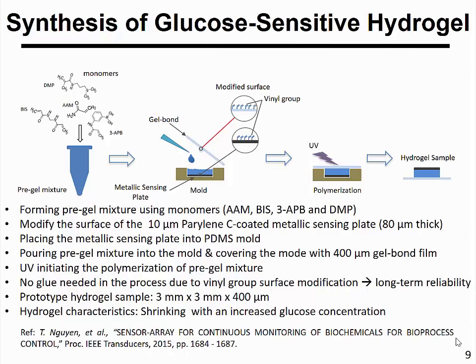An important design aspect is that during the whole process, we do not need any glue to secure the position of the sensing plate or the hydrogel. This is due to the surface modification process shown here. After surface modification, there is something called a vinyl group on the surface of the metallic sensing plate, which is a double bond and will naturally combine with the hydrogel during the polymerization process. The reason this is critical is for long-term reliability, because if you use glue to secure the position of any of these parts, then during the glucose cycle, the hydrogel will shrink and expand, and over cycles and cycles, you will see some delamination that limits the longevity of the sample.